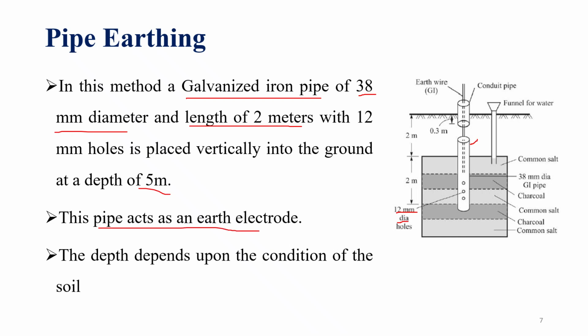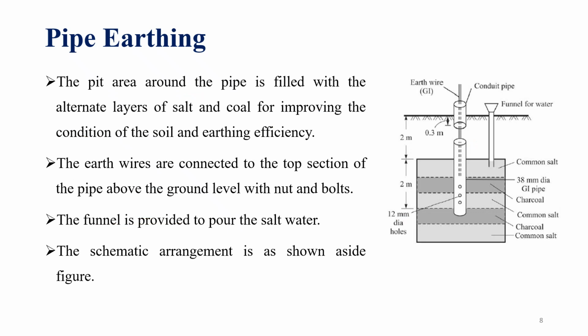Next, this pipe is going to act as an electrode and the ground wire is connected to this electrode through a GI pipe. Depending upon the conditions of the soil and the resistivity of the soil, the length and depth of the pit is going to change, similar to the plate earthing. After placing the electrode, the remaining surrounding pit area is going to be filled with layers of common salt and charcoal in alternate way. First salt, next charcoal, salt, charcoal, salt, and charcoal. Like that, we are going to fill the entire pit. And again, here also, we are going to provide a funnel so that we can periodically pour salt water in order to increase the effectiveness of the earthing.